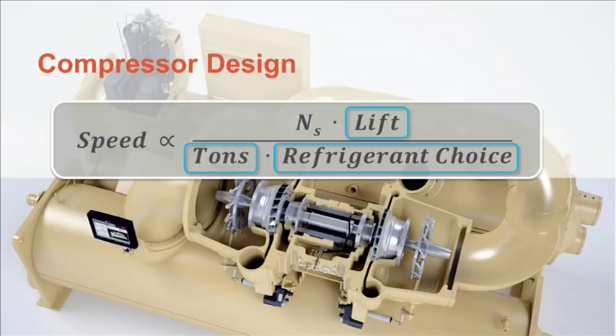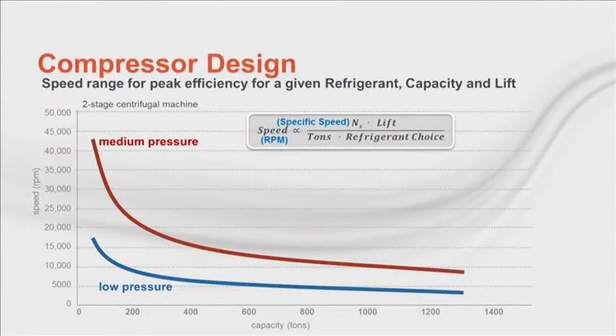These three items drive the design's specific speed, or more simply put, the optimum speed to spin the impeller in order to achieve the best efficiency from that impeller. This more readily translates into RPM. Now, please recognize this formula has been simplified to illustrate the correlation between these variables and how they relate to the speed of the impeller. Let's take this a step further and look at how this would apply to a chiller. Now, you'll see that RPM is on the y-axis and tonnage on the x-axis. As you decrease in tonnage, RPM needs to increase to drive towards the design's specific speed.